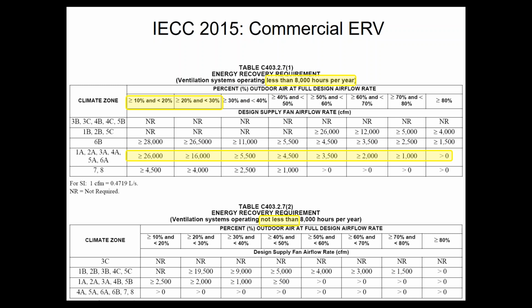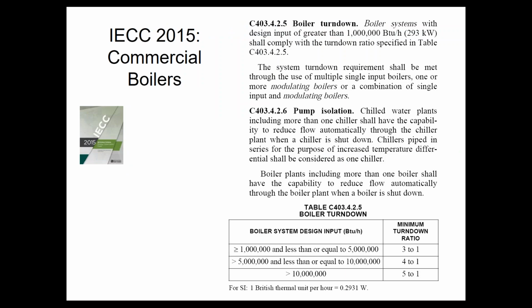Additionally, there's now another table for systems that operate basically year-round. There's 8,760 hours in the year. If your system's designed to operate most of the year, 8,000 hours, then for climate zones in Illinois and Wisconsin, anything more than 10% outside air, you have to have an ERV automatically. This is going to include a lot of your hospital-type projects and things like that. Technically, it would include, I don't know, a 24/7 gas station or something like that. So that's when ERVs would be required.